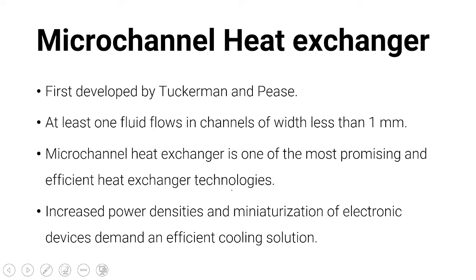So what is a Micro Channel Heat Exchanger? The main working principle of a Micro Channel Heat Exchanger is the same as that of normal heat exchangers like shell and tube heat exchangers. But the difference is that at least one fluid flows in channels of width less than 1 mm. In mechanical terms, the hydraulic diameter of the channel is less than 1 mm. It was first developed by Tuckerman and Pease.